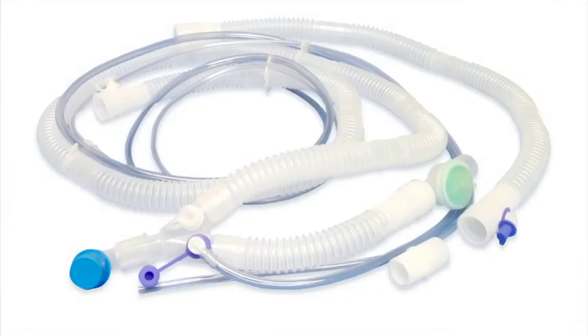HT70 can be set up with either 22mm or 15mm internal diameter, non-proprietary breathing circuits. Remember that the quality of the circuit and exhalation valve will impact the performance of the ventilator. So for the best performance, you should use a good quality circuit. We'll use a disposable J-style circuit to demonstrate breathing circuit setup.